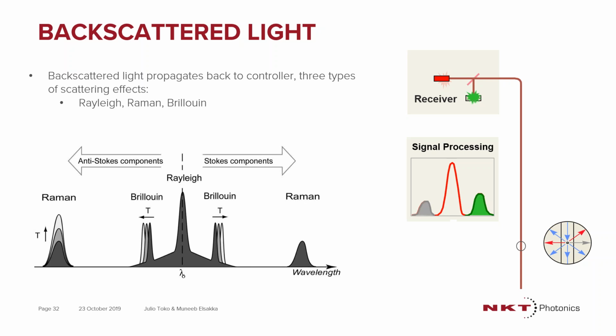One advantage of how the technology works is this was, let's say, an effect in telecom that they did not want to see. It changed the laser light at different wavelengths due to temperature, but in our case, we benefited from that. Most of the other vendors of fiber optic linear detection loved it because they can turn it into a sensor. So essentially now, knowing the speed of light within the cable, we can tell you exactly, within 10 inches, where the temperature is rising, at what rate it's rising, and what we can do with that.